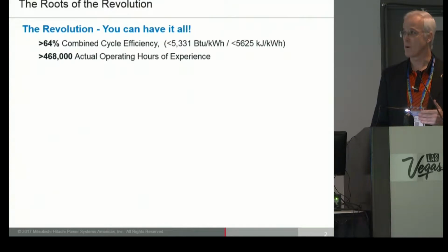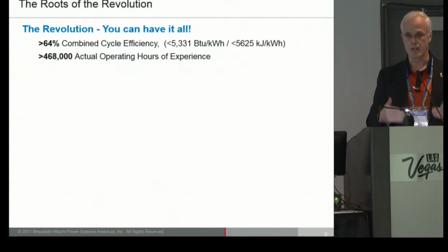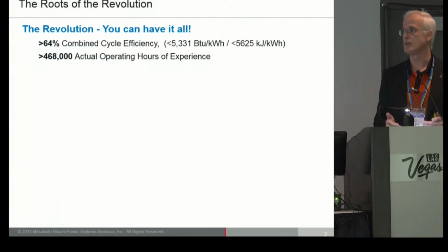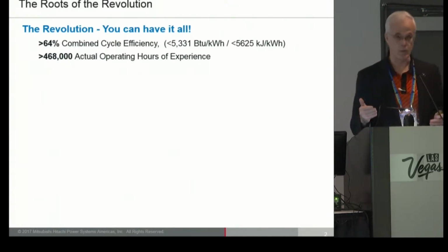We have over 468,000 actual operating hours on our J fleet at this time. It first came out as steam cooled. This is a process we've gone through, introducing high temperature, high technology equipment. Steam cooled comes first because it's easier to use until air cooled technology gets to the level where you can get that same temperature, so you can get the better efficiency even with air cooling.